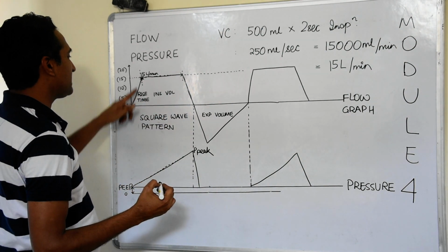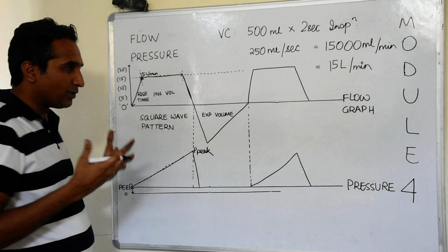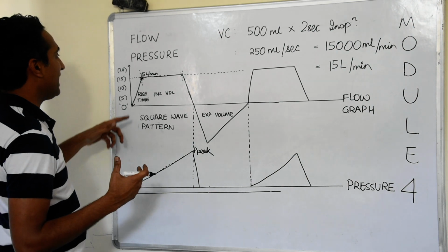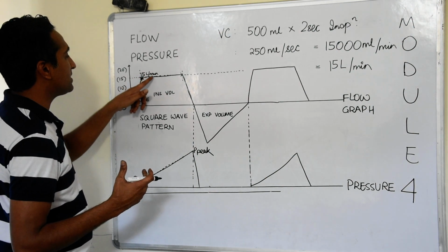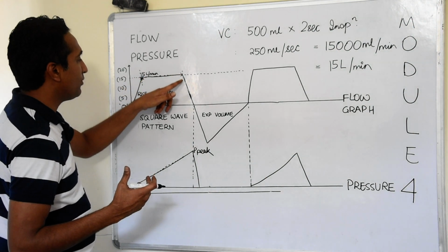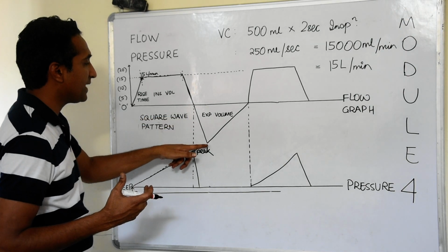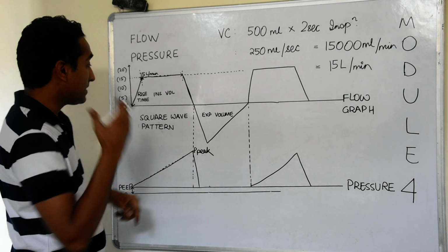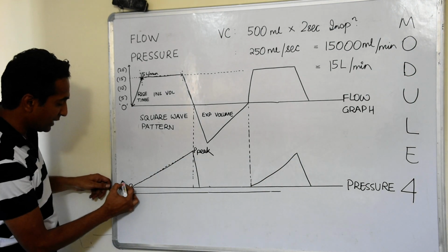and this can be set according to the air hunger of the patient. It's not such an important setting to do. And then the flow remains constant, the flow drops, the breath goes into expiration, and again a new breath starts.